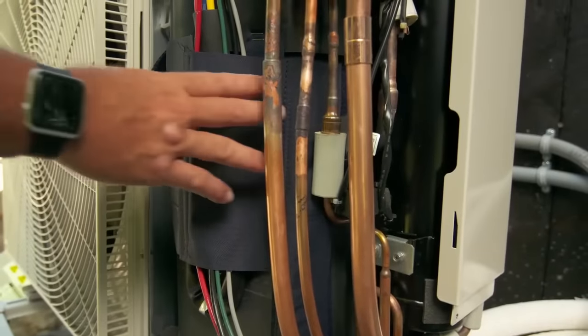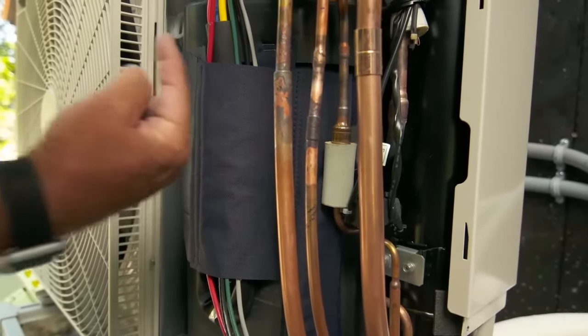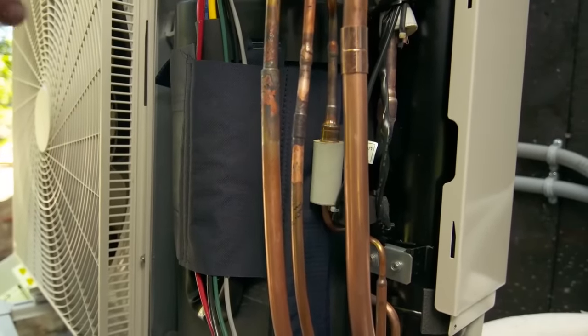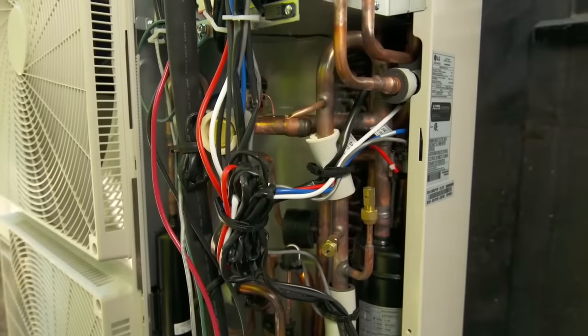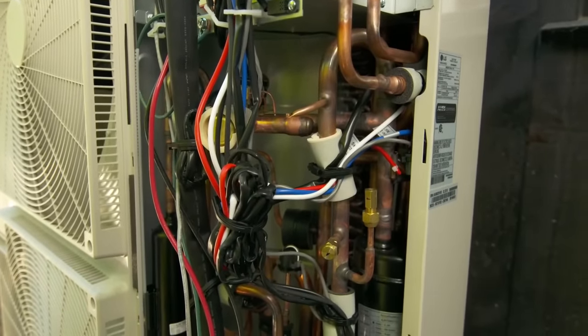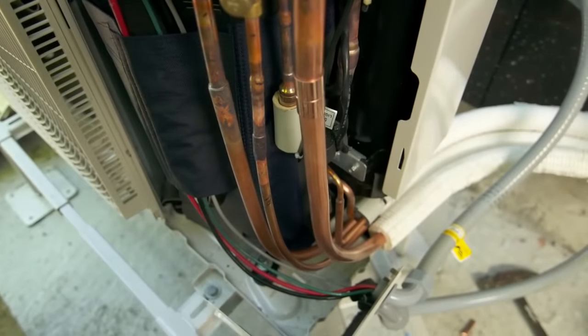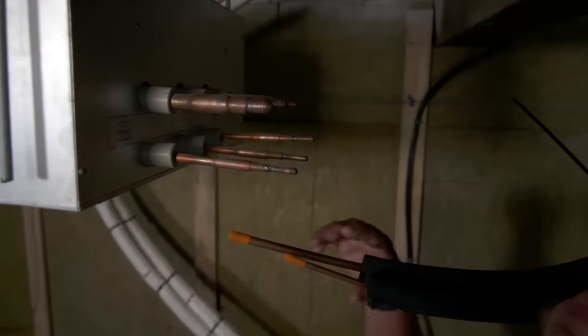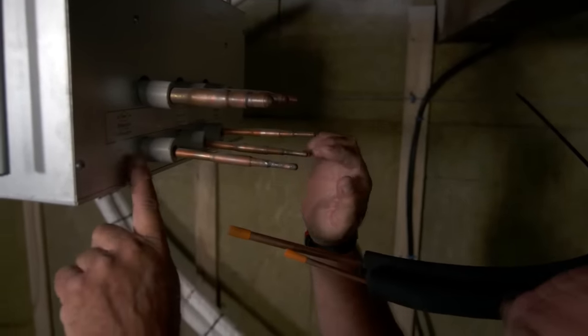One other piece of technology we should talk about is this, which we just showed on a job site. A regular unit can either cool the building or heat the building. But there are moments in spring and fall where the sunny side wants air conditioning and the north side wants a little heating. So here's a heat recovery unit: instead of two pipes, there are three pipes between the inside unit and a distribution box, so you can take heat into the building or take heat out of the building. It's like commercial VRF, but now available for single phase 110 volt or 220 volt supply. It comes into a distribution box, so you can simultaneously heat one side of the building and cool the other side.